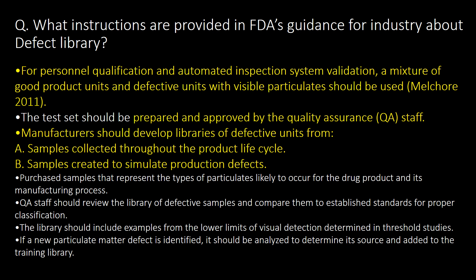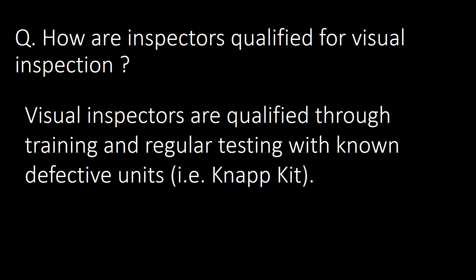What instructions are provided in FDA guidance for industry about the defect library? For personnel qualification and automated inspection system validation, a mixture of good product units and defective units with visible particulates should be used. Visual inspectors are qualified through training and regular testing with known defective units, i.e. the Knapp Kit.